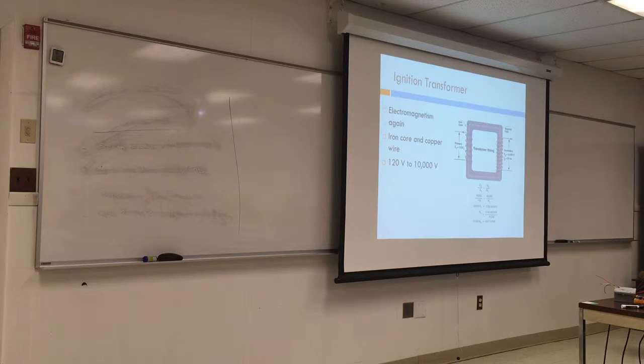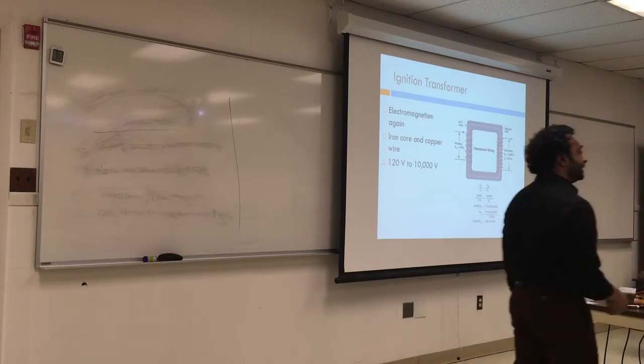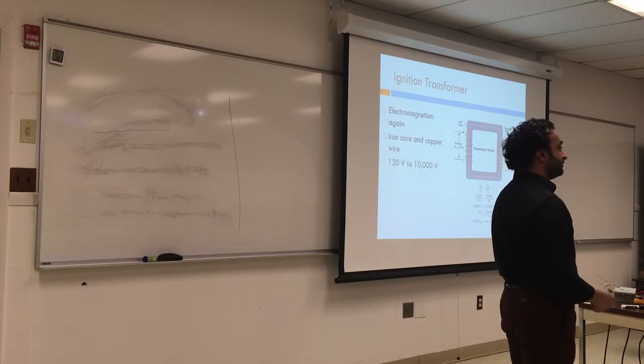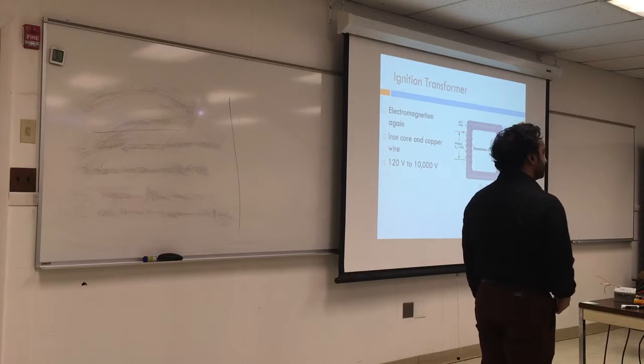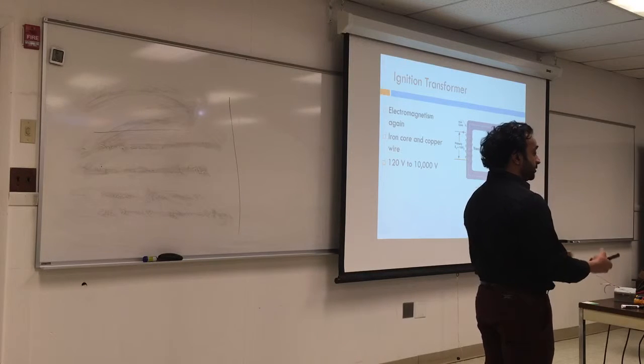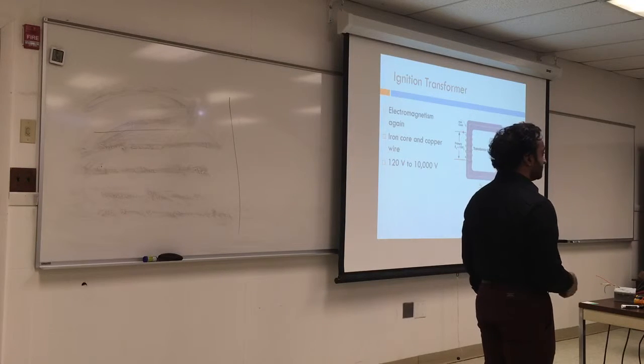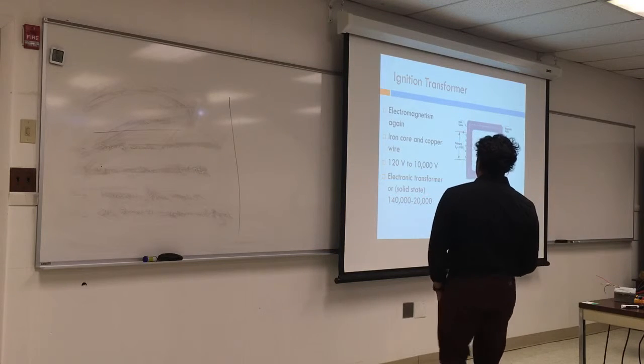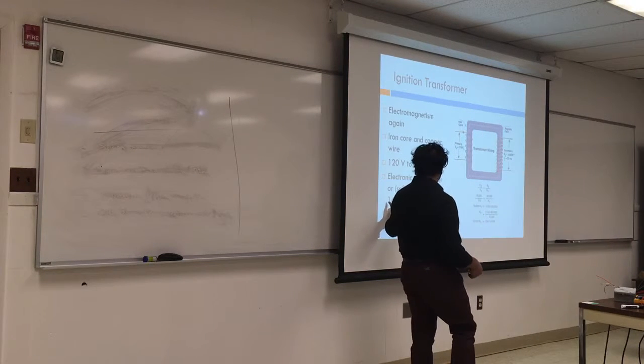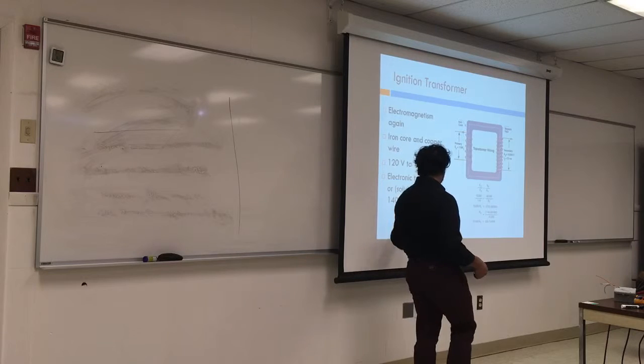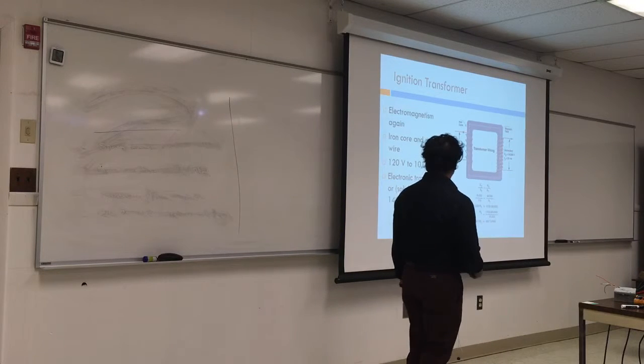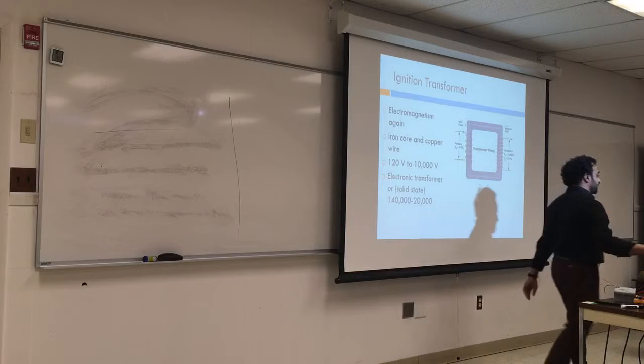What color is it supposed to be in theory? Blue. If it's orange, that means it's a little bit weak. It's not going to give you enough. But the igniters? Yeah. You see this one, it was blue and purplish. If it's orange or yellow, it means it's not hot enough to ignite. Can it be that color? Yeah. If you push them further, it's going to be orange. Electronic transformers are usually between 14,000, 140 is 14, not 140, 14,000 and 20,000. They're also called solid state.